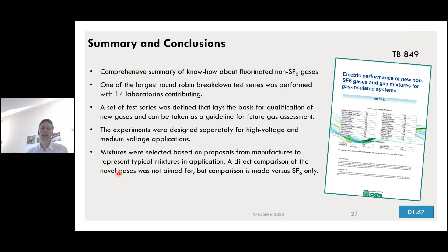It is documentation of one of the largest round-robin breakdown test series I'm aware of. 14 laboratories all over the world contributed more than 270 test series. A complete set of 14 test series was defined, which lays the basis for qualification and comparison of future non-SF6 gases. The experiments were for high voltage and for medium voltage applications. And we have also done representative measurements on mixtures that were proposed by manufacturers. So the C4 measurement I showed you, there were C5 mixture measurements, there were CF3I measurements and HFO measurements, and of course, comparison to SF6.